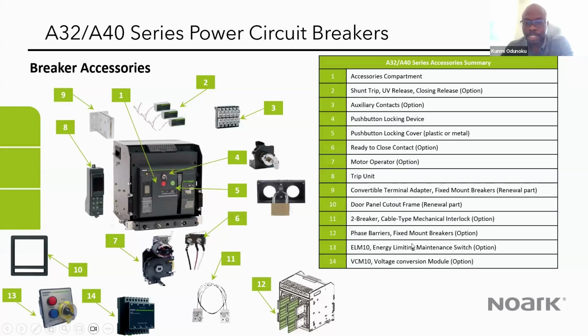We have the energy limit maintenance switch, which is number 13 here. The function of that is, during maintenance, you want to be able to put the breaker into an arc reduction mode remotely. You don't want the personnel to go in front of the breaker to do that. So they can remotely put that breaker in that maintenance mode, which is a mode that reduces the arc flash that can happen in such a situation.